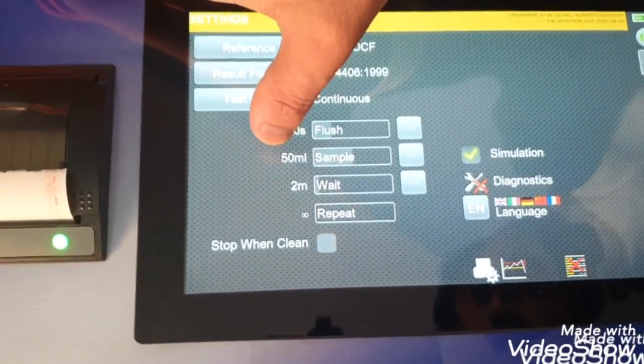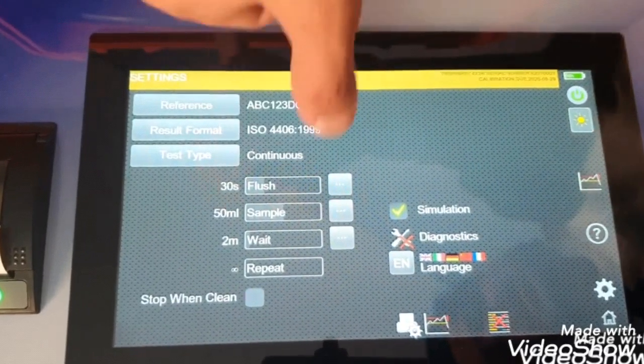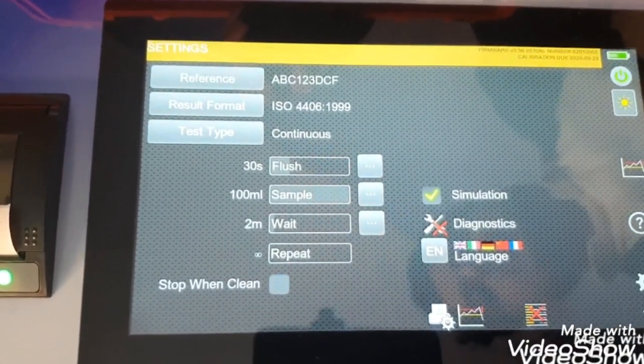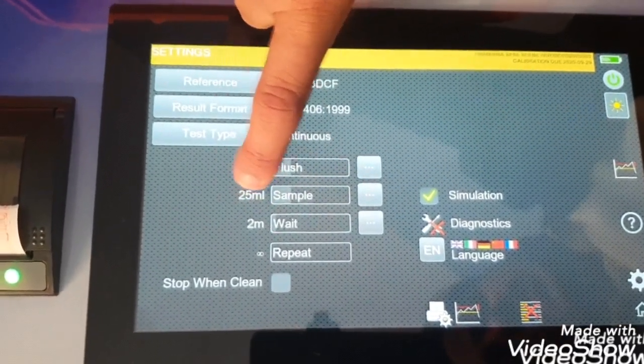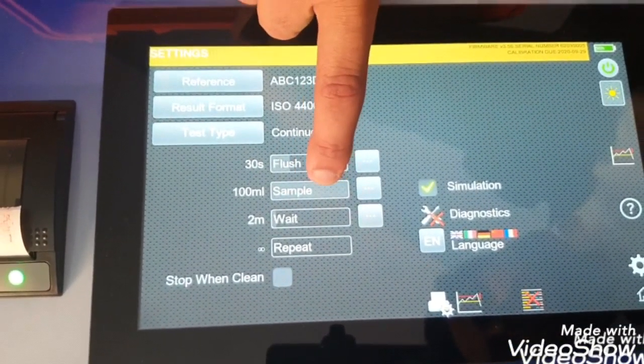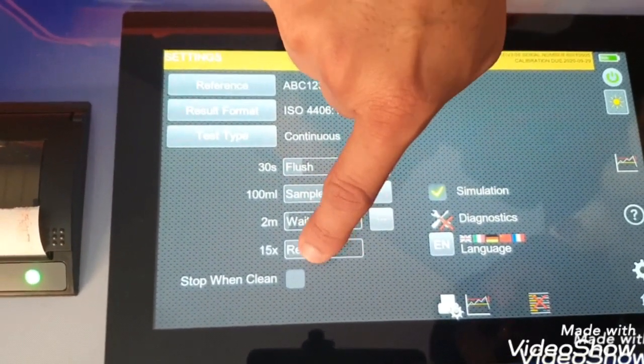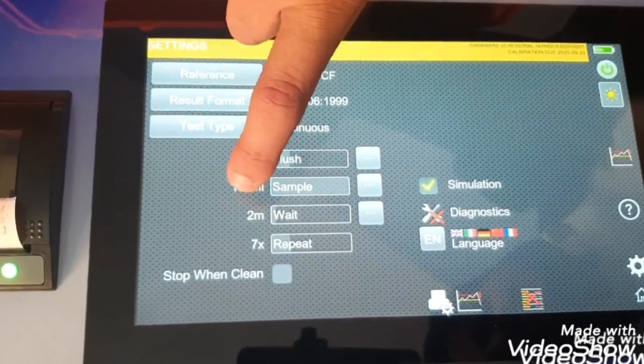Here is the sample volume setting — this feature is not found in most particle counters available in the market. We can set the test volume from 25 ml to 100 ml. The 100 ml test volume is specified as per the standard. Most particle counters take a lesser volume and then integrate the results to show readings, but here you can do the maximum of 100 ml. You can also set the interval or wait time between multiple tests.